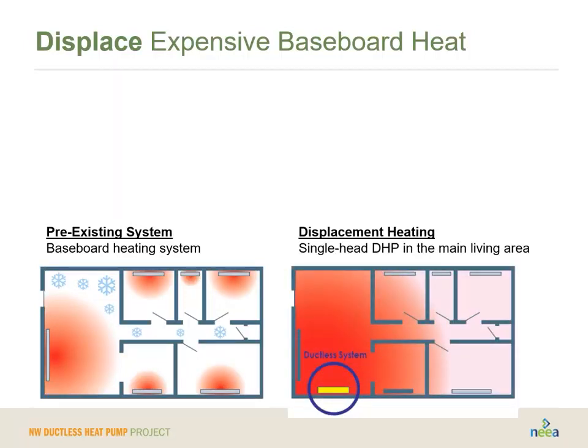So with displacement, we put that single head DHP in the main living area, and it's going to do the bulk of the job for the parts of the home that people spend the majority of their time. Now, you still want to use your baseboards or your wall heaters in the bedrooms particularly, and you may want to turn those down a few degrees, 2 or 3 degrees. And it turns out most homeowners are okay with their bedroom being just a couple degrees cooler than the main body of the house. So with this approach, the ductless heat pump does the lion's share of the work for heating and cooling of the home, and you still have these baseboards or cadet wall heaters for those instances where you still need some additional heat throughout the house.